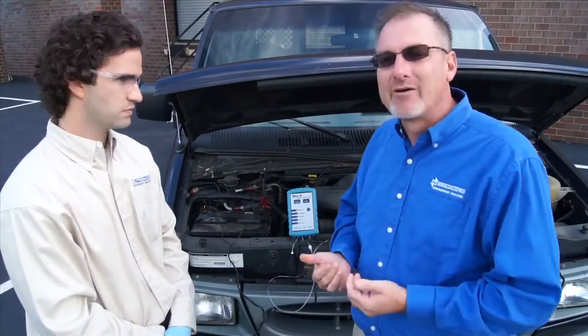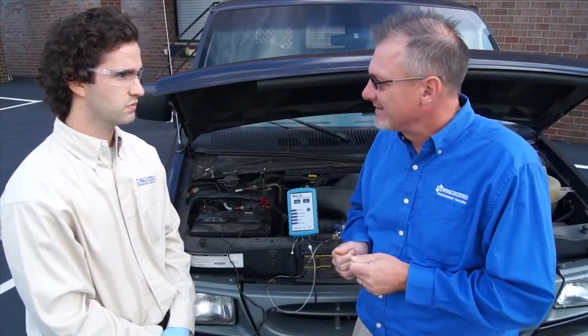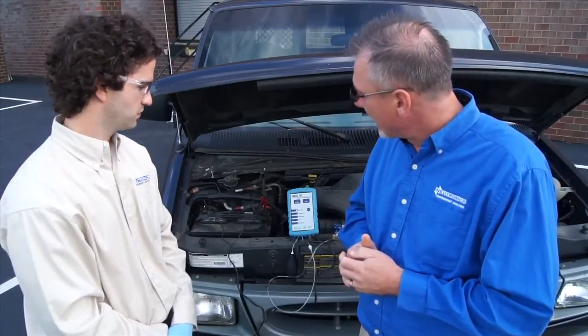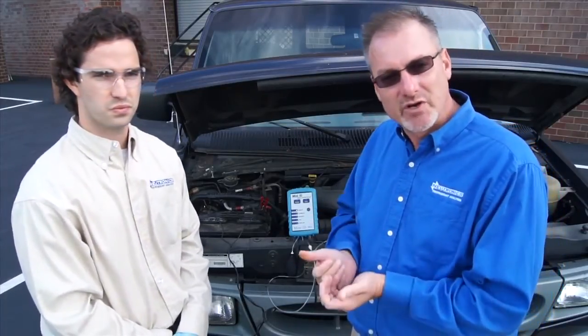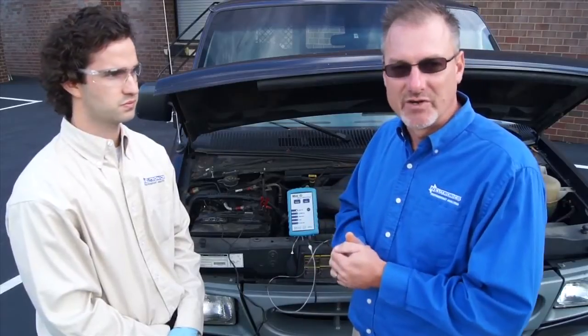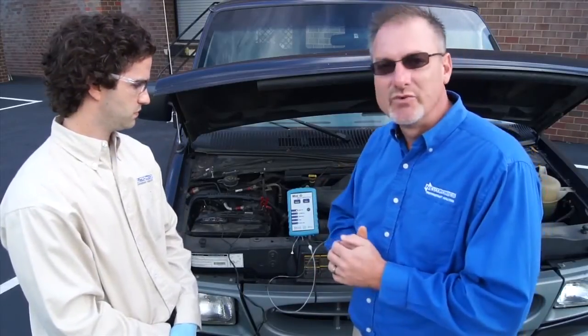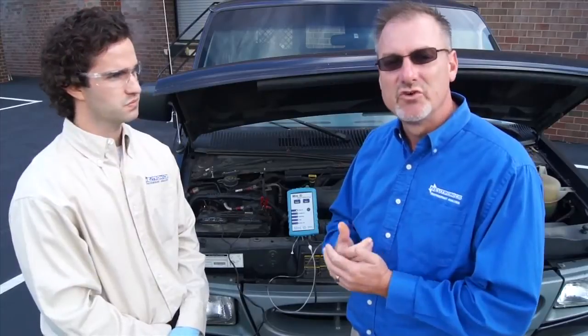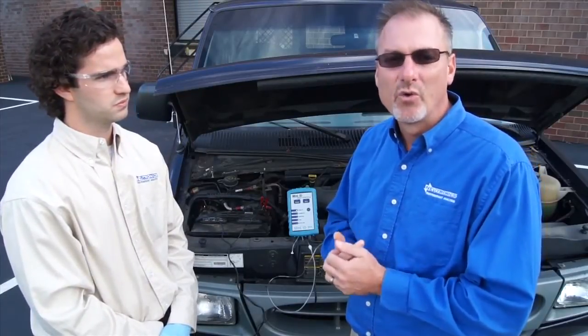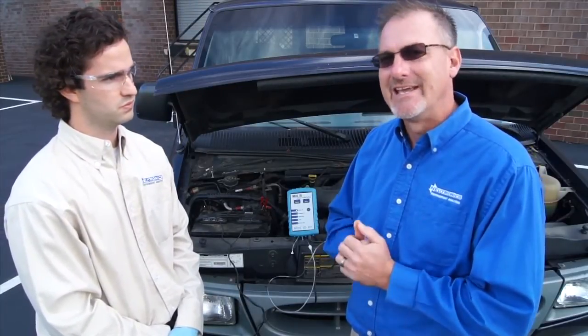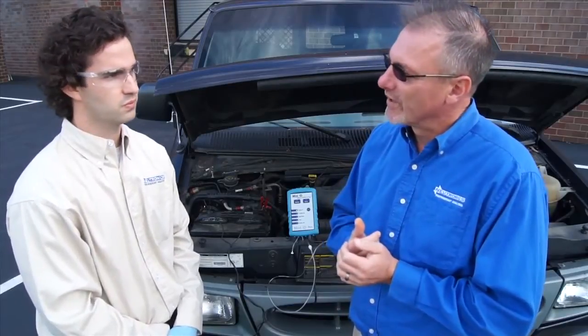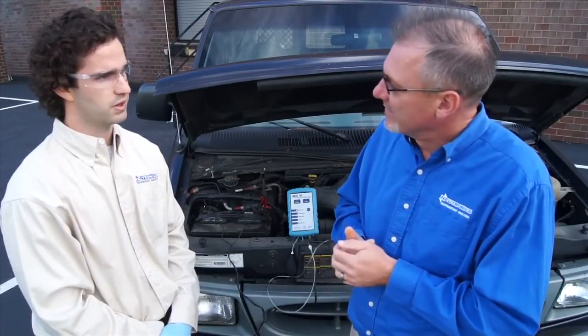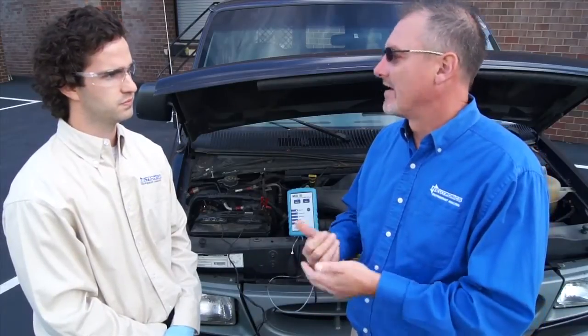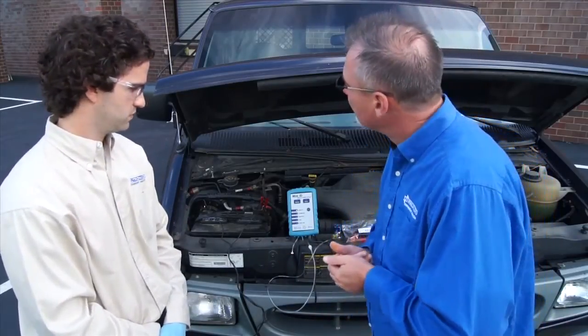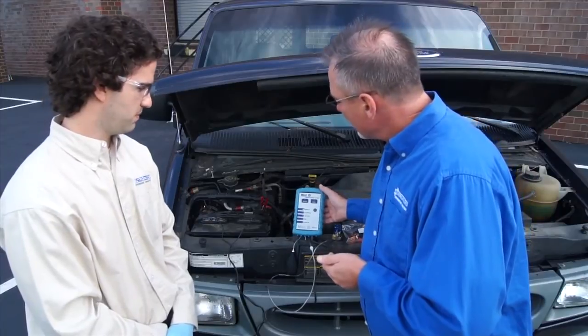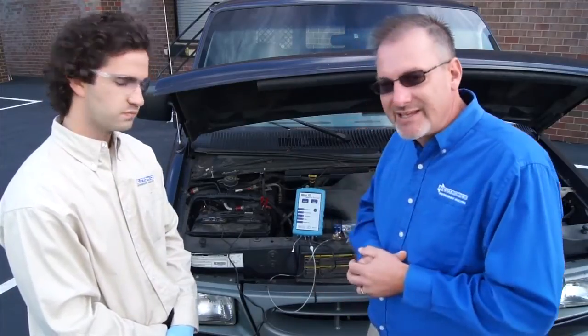Warm up takes about 60 to 90 seconds, I think. Yeah, something like that. And then it'll go into a calibration mode, and then we'll go into an analyzing mode. The device is designed to identify refrigerant if it is good 134A using only a pass or fail indication. If it's good 134A, it's 95% or better. Correct. If it's bad 134A, it's 95% or less. So, we're about done on warm up. Just about done warm up. There we go. We got a blinking calibration light.